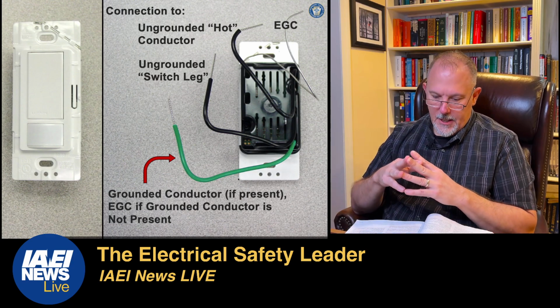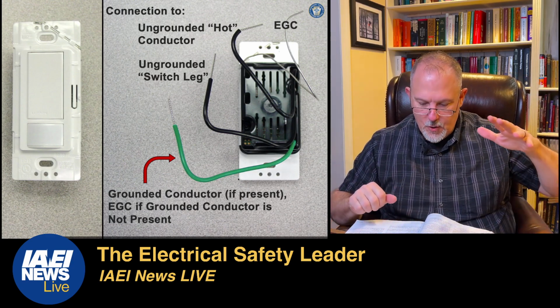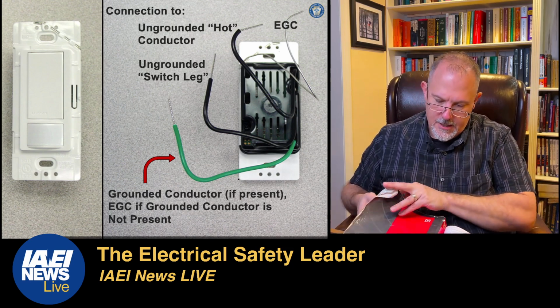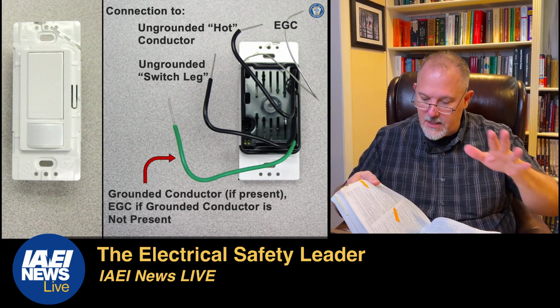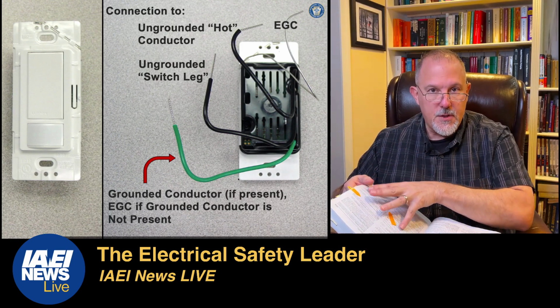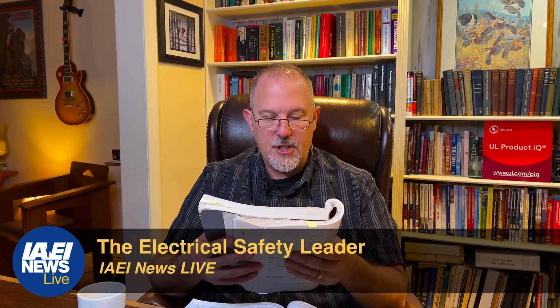I like it. So, we saw the introduction. We saw that it changed in the 17 code. So the 14 introduces this. The 17 said, hey, we need this other section over here to address the proper installation of these products. And oh, by the way, we put this exception in, and I started reading this. It says the number of electronic lighting control switches on a branch circuit shall not exceed 5, and the number connected to any feeder on the load side of a system or main bonding jumper shall not exceed 25. For the purpose of this exception, a neutral bus bar in compliance with 200.2(B) and to which a main system bonding jumper is connected shall not be limited as to the number of electronic lighting controls.